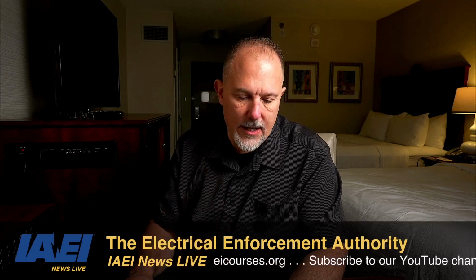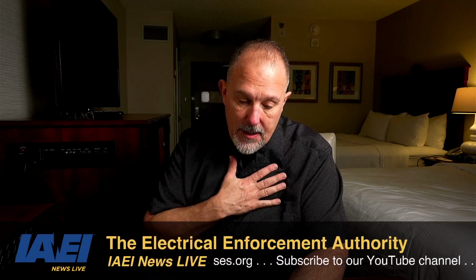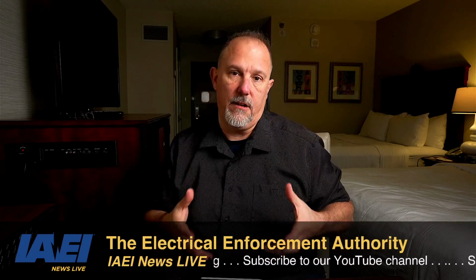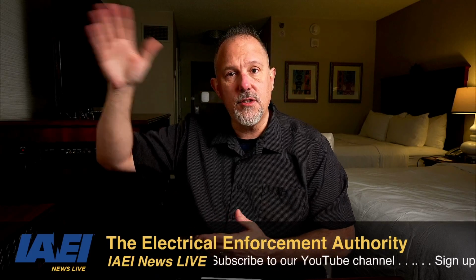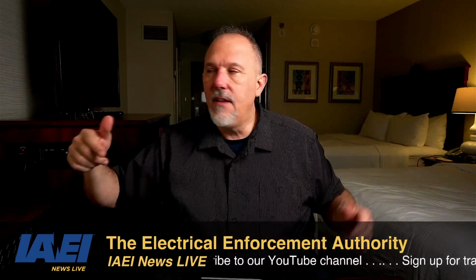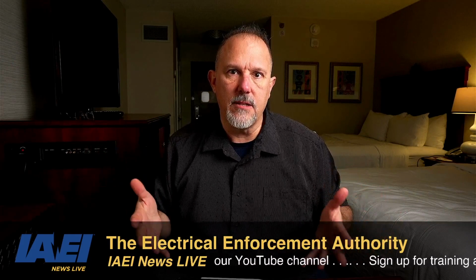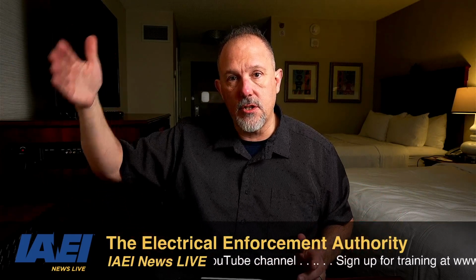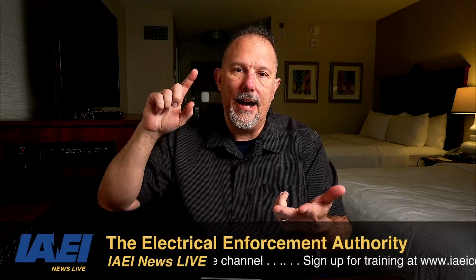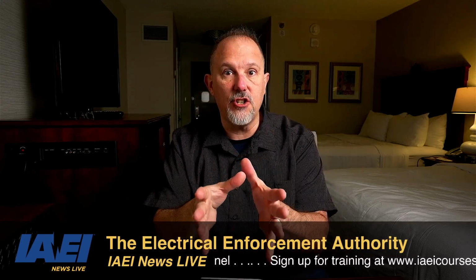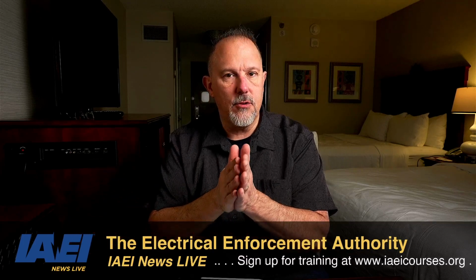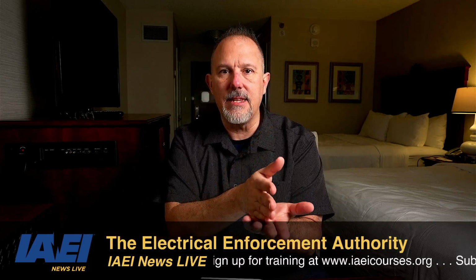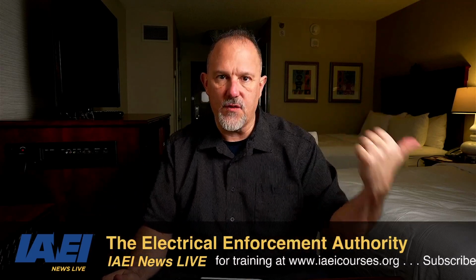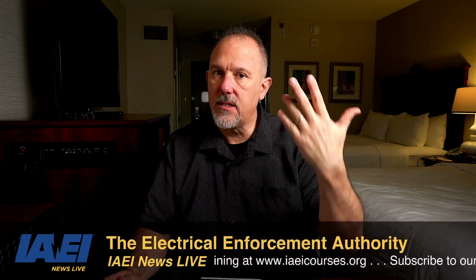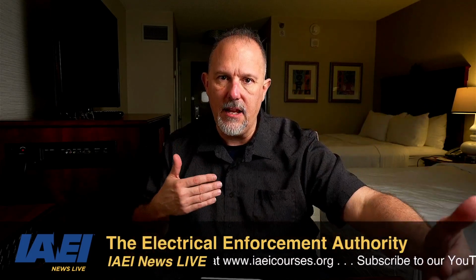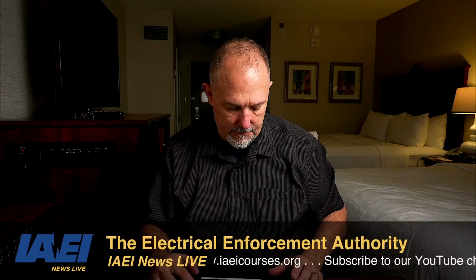And then they have 3-wire direct current generators. So in my opinion, from an overcurrent protective perspective, you've got to understand, is there a breaker in there? If there's a breaker in there, then you know how to size your feeders. If there's no breaker in there, then now you've got to figure out, how do I size my feeders, right? Because there's no protection at the source. Now, what's the length of my conductor? How for the terminations, just like in a transformer, secondary conductors. I don't have protection at the point of where I connect to that transformer. So now I'm into 240 transformer secondary conductors. I'm into a specific length and how I need to protect those conductors, all that jazz.